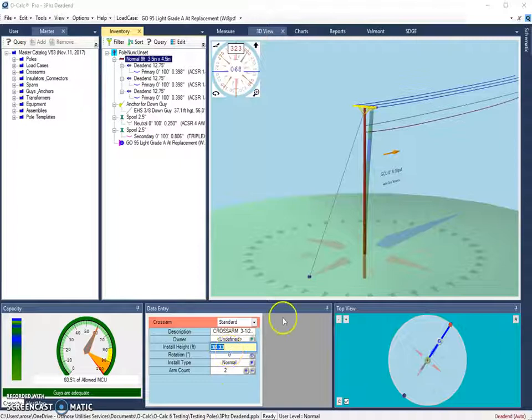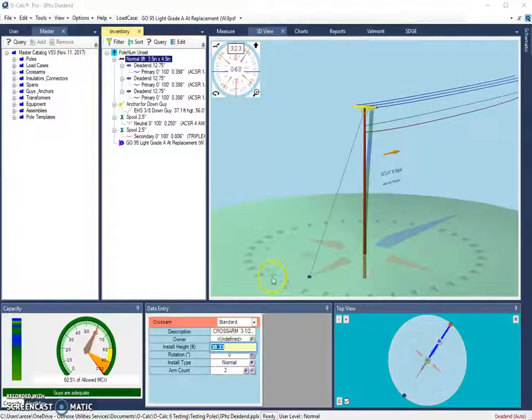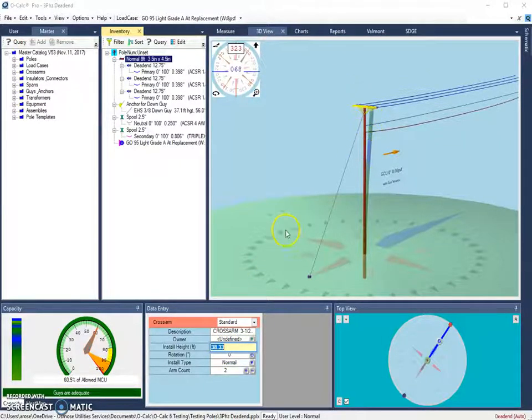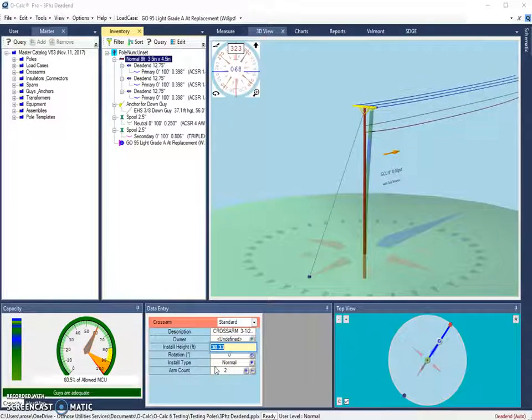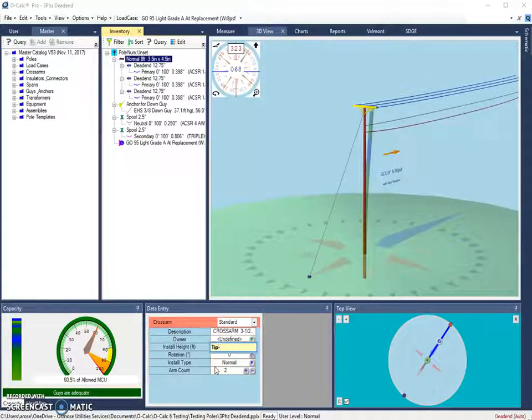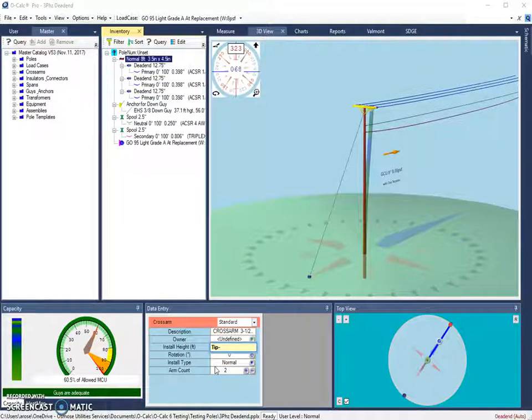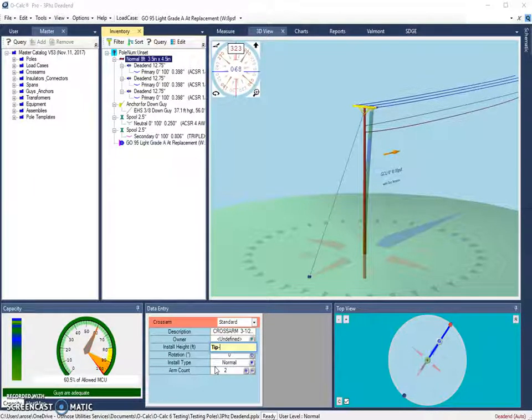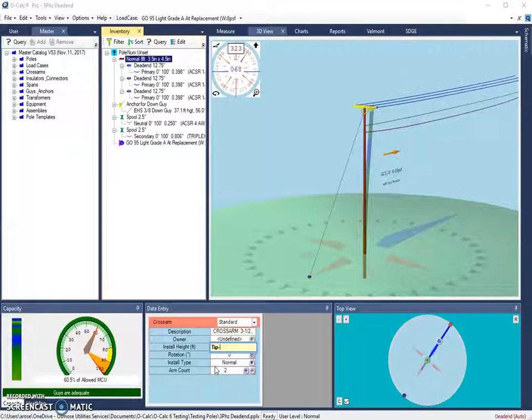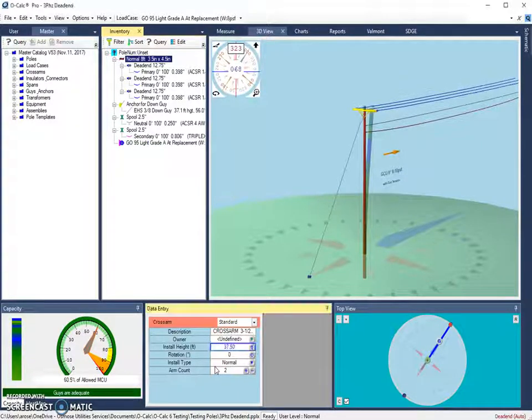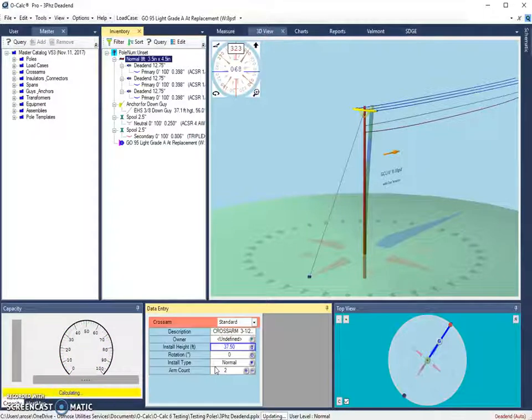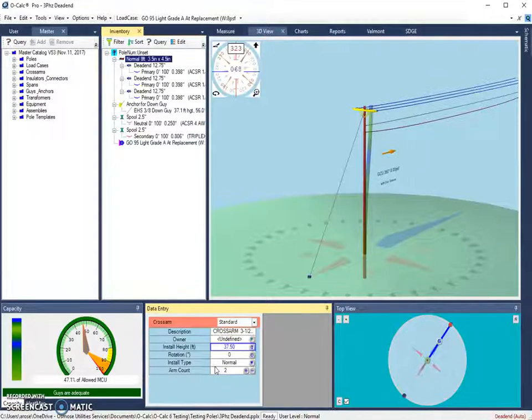So let's say we wanted to move this cross arm a certain distance below the tip of the pole. This can be done using the TIP minus shortcut, which allows a user to put an object a certain distance away from the tip of the pole. So let's say we wanted to move this one foot below the tip of the pole. We could do TIP minus one and hit enter. And it will move our cross arm down to one foot below the tip of the pole.